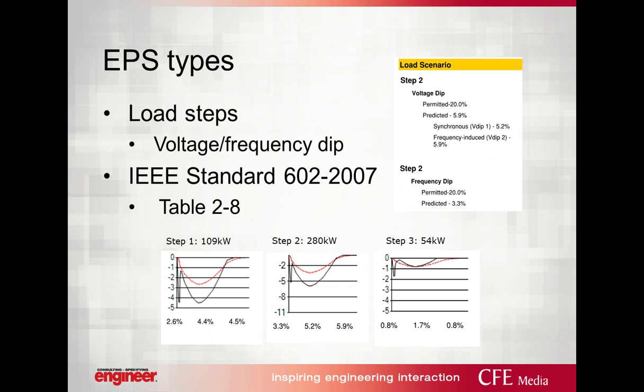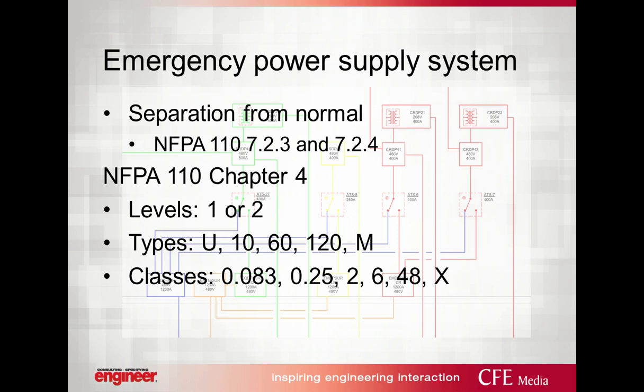Another handy reference I listed is another table in IEEE standard 602, and that is emergency generator loading measurements for 74 locations across the country. And they break it out by watts per square foot and the location. Now, an EPSS, or Emergency Power Supply System, as defined in NFPA 110, consists of distribution electrical gear and transfer switch equipment. And NFPA says that this equipment has to be physically separated from normal service. And we'll get into that here in another slide.